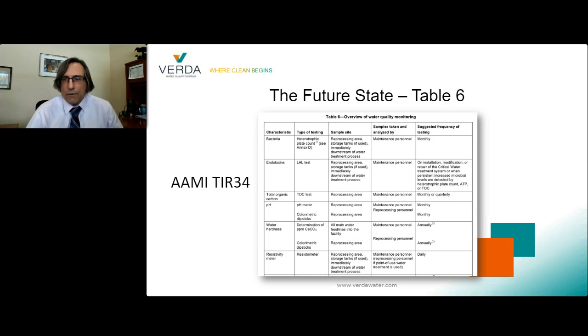If we look at the bottom of this table, we see that resistivity, the inverse of conductivity, will be measured using a meter in the same location as the bacteria testing happens, only it will need to be done daily by the maintenance person. Again, this is an example. AAMI is not recommending that the maintenance person is the only one that can do it. It can be anyone properly trained to use the meter, a meter that is properly calibrated per its own IFUs.